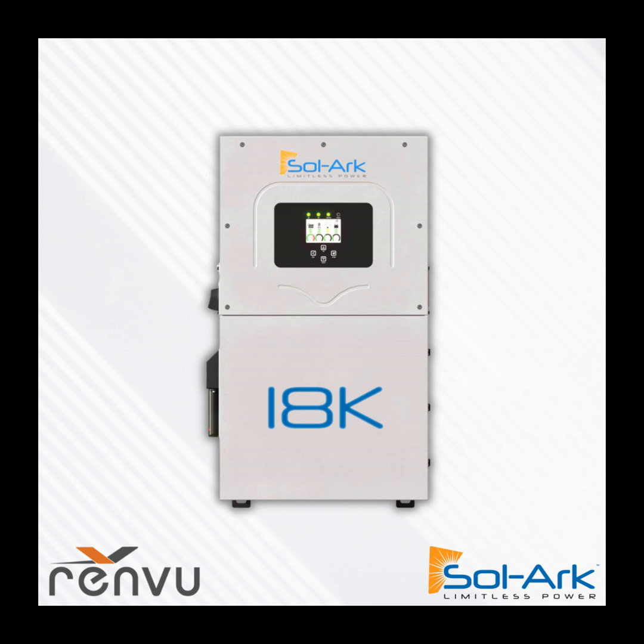And so what this looks like is you might get a 208 volt electric bill, and you look at the demand charge, and it's a 150 kilowatt demand charge, and you say, okay, I'm going to sell you 1 inverter with 1 battery cabinet and 2 transformers and an AccuPanel, and that's going to be my 208 volt standard bid for peak shaving or time of use arbitrage.